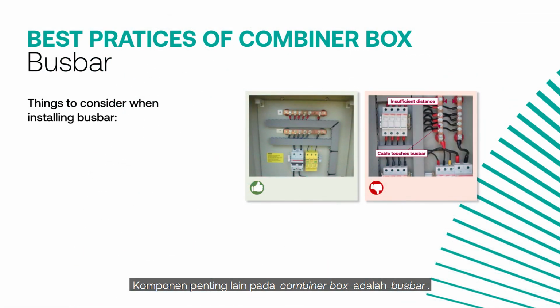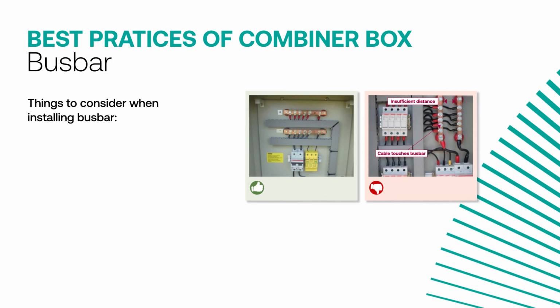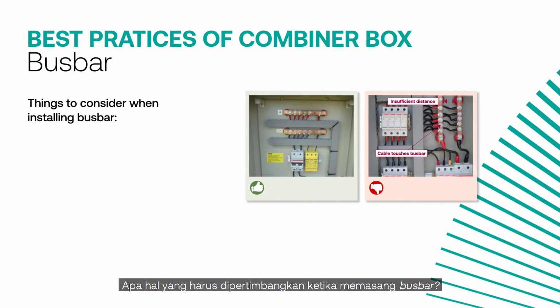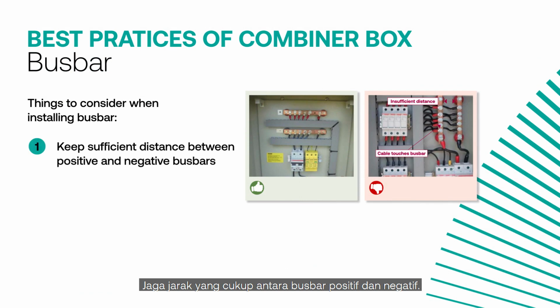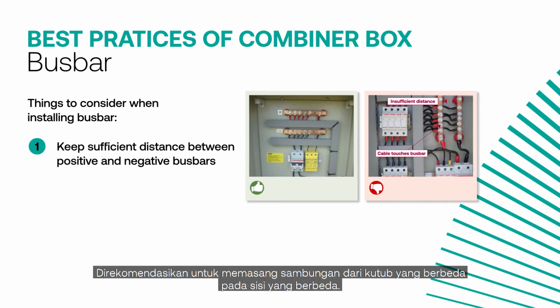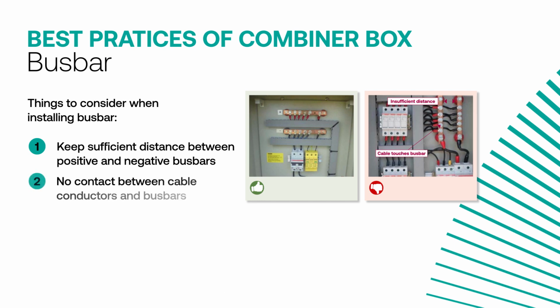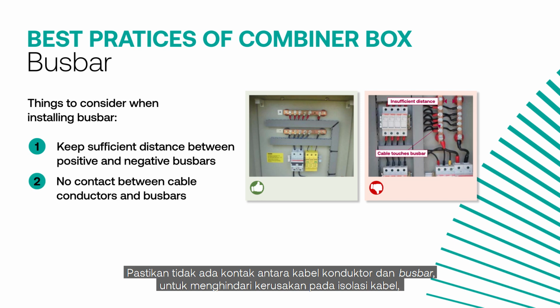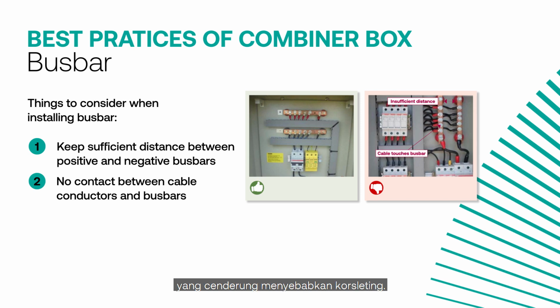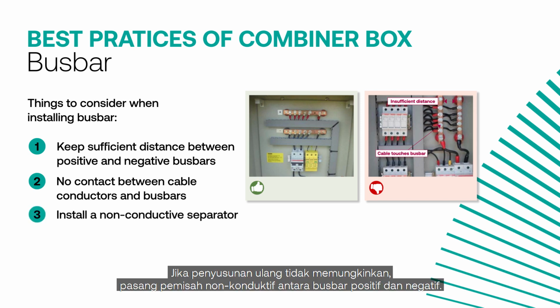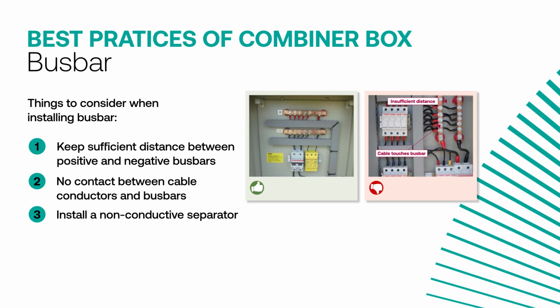Another important component of the combiner box is the busbar. What are the things to consider when installing a busbar? Keep sufficient distance between positive and negative busbars. It is recommended to install connections from different polarities on different sides. Ensure that there is no contact between cable conductors and busbars to avoid damage to the cable insulation, which is prone to short circuit. If rearrangement is not possible, install a non-conductive separator between the positive and negative busbars.